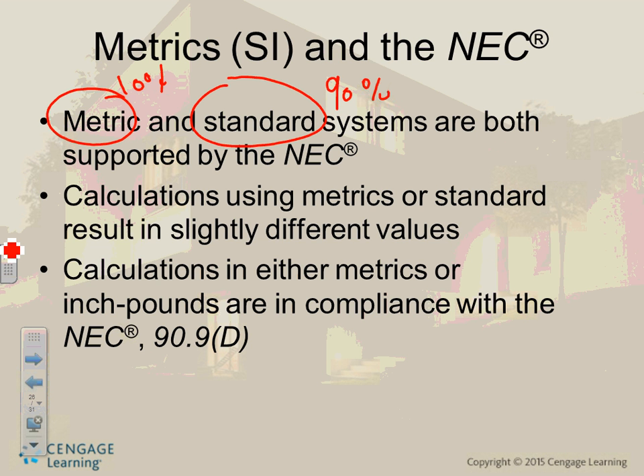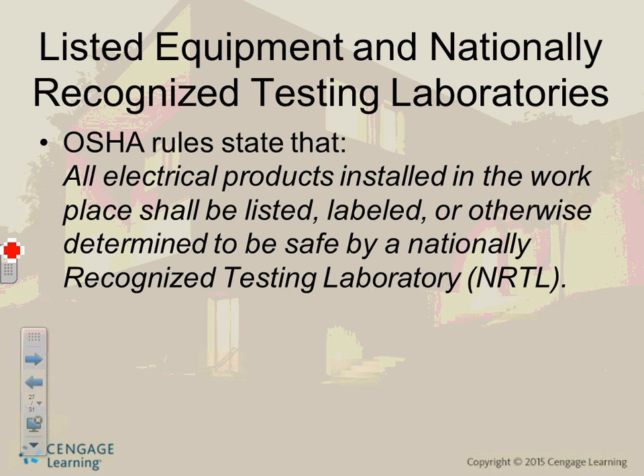So if you have a project in Brazil and you need to size a service for it, you can use meters. I can't remember how many volt-amperes per square meter, which is equivalent to 3.5 volt-amperes per square foot for an office building. You do the equivalent for meters, multiply by how many square meters, and you size the building. Either one will meet compliance with the code book, whether metric or standard.